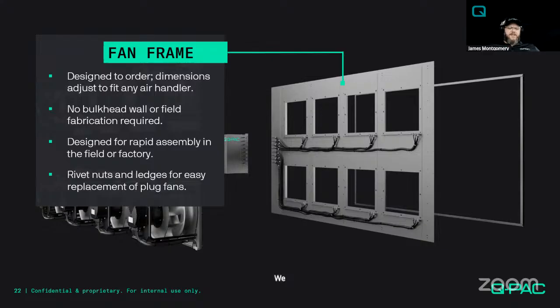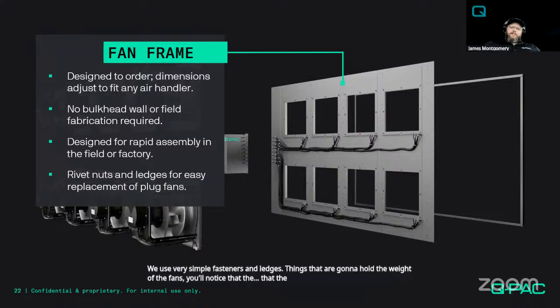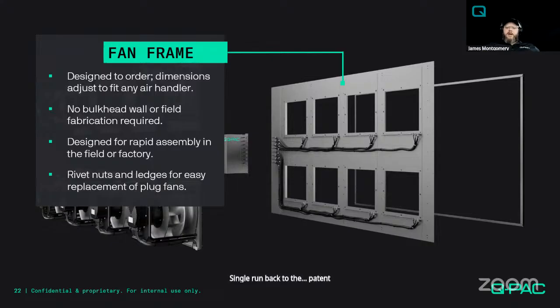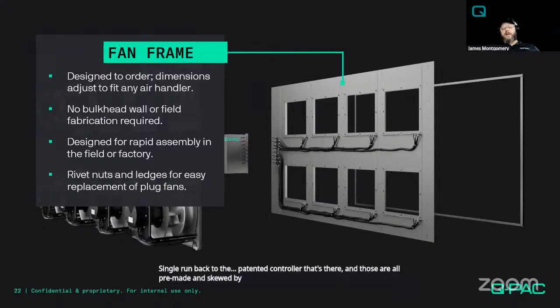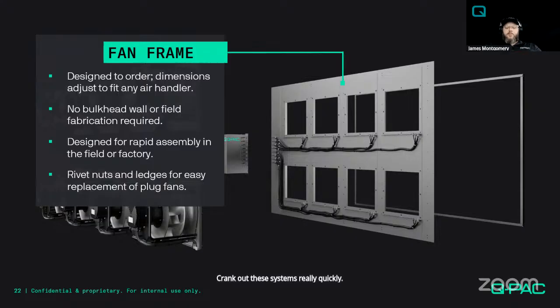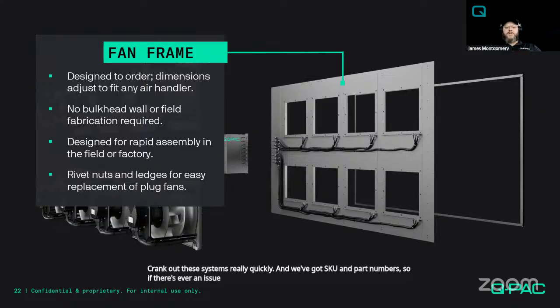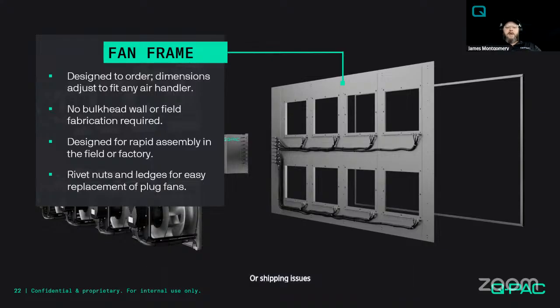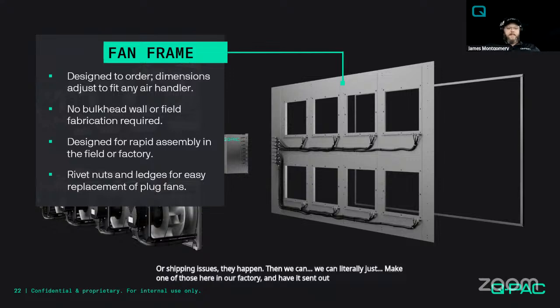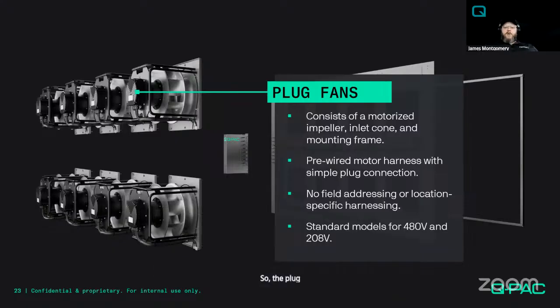We use very simple fasteners and ledges, things that are going to hold the weight of the fans. You'll notice that the frame wires are already on this picture. And so those frame harnesses are all single run back to the patented controller that's there. And those are all pre-made and SKUed by us here in our factory. And so what that does for us is it means that we can actually crank out these systems really quickly. And we've got SKU and part numbers. So if there's ever an issue in the field and one of those needs to be replaced or shipping issues, they happen, then we can literally just make one of those here in our factory and have it sent out overnight to you. So the plug fans, motorized impellers, inlet cones, and a mounting frame, pre-wired harnesses.